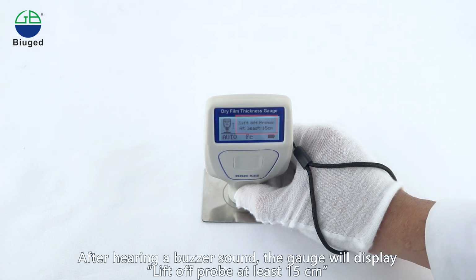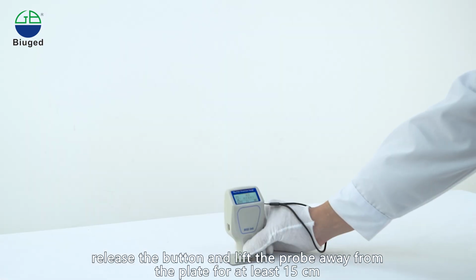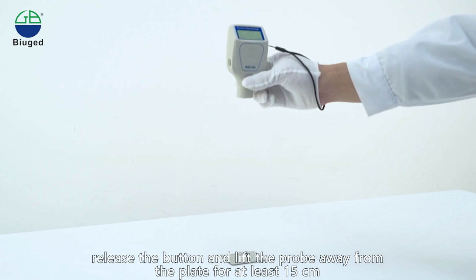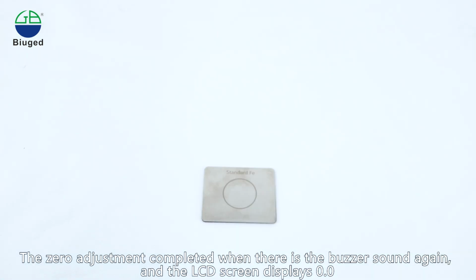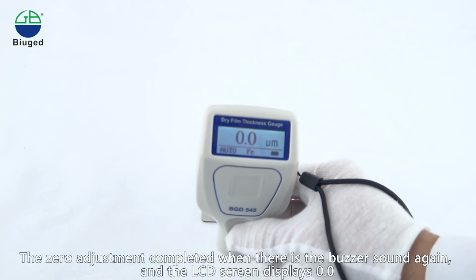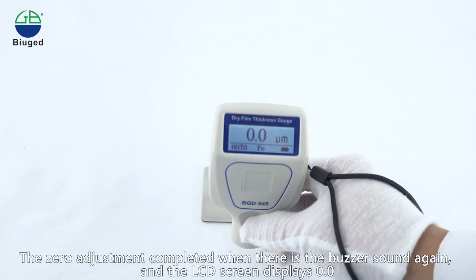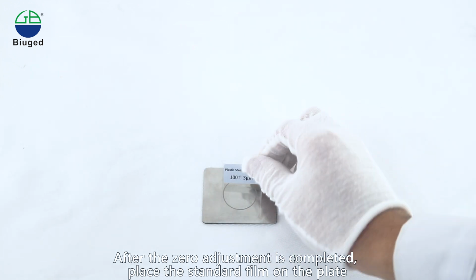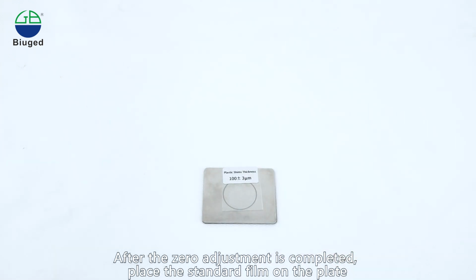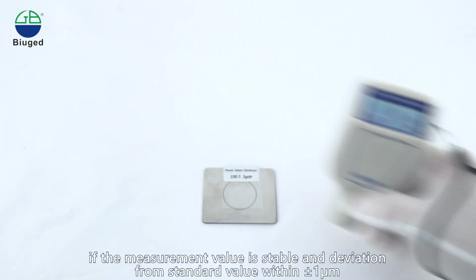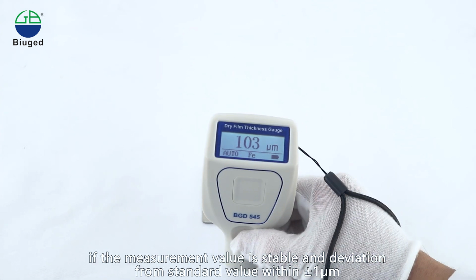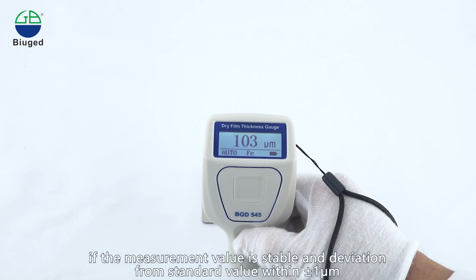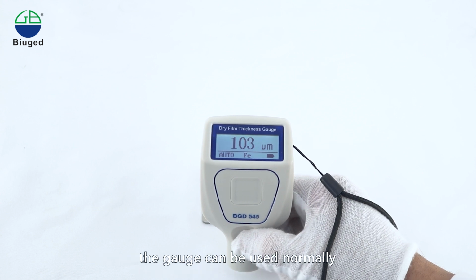After hearing a buzzer sound, the gauge will display lift-off probe at least 15 centimeters. Release the button and lift the probe away from the plate for at least 15 centimeters. The zero adjustment is completed when there is the buzzer sound again, and the LCD screen displays 0.0. After the zero adjustment is completed, place the standard film on the plate. If the measurement value is stable and the deviation from the standard value is within plus or minus 1 micrometer, the gauge can be used normally.